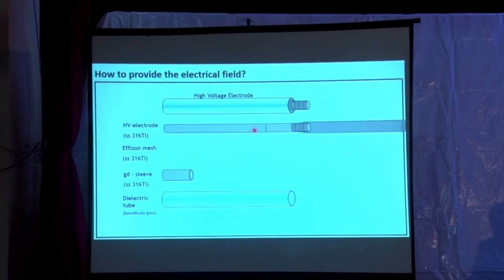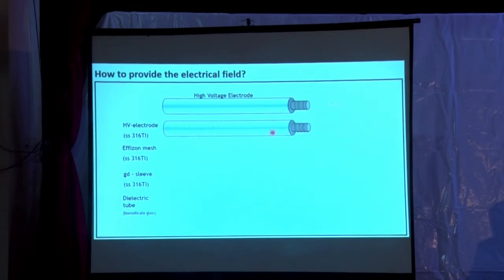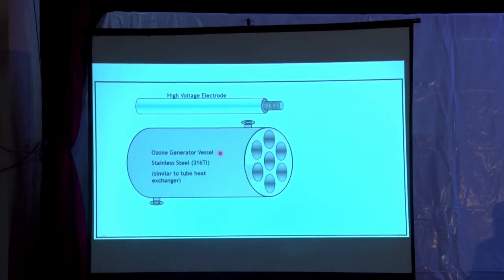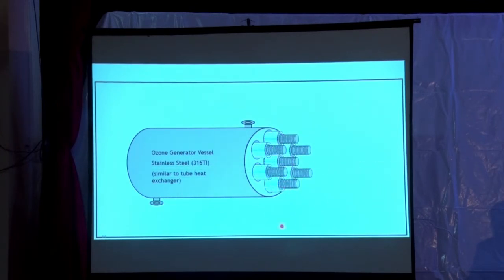Just above this, we have an Effizon mesh, and before that we have a gas distribution sleeve. The oxygen enters through this gas distribution sleeve, and the Effizon mesh allows the oxygen to be converted into ozone. Above the Effizon mesh, we have a dielectric tube. It's borosilicate glass. This is the electrode. All 20,000 electrodes are in a generator that is like a shell and tube heat exchanger, with 20,000 tubes. In each tube, these electrodes are inserted.